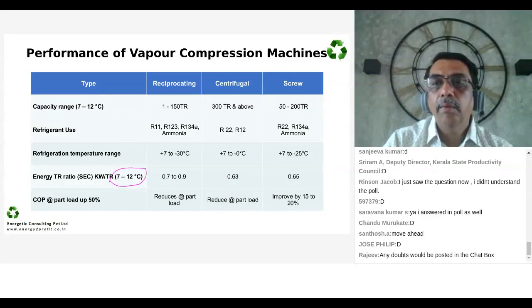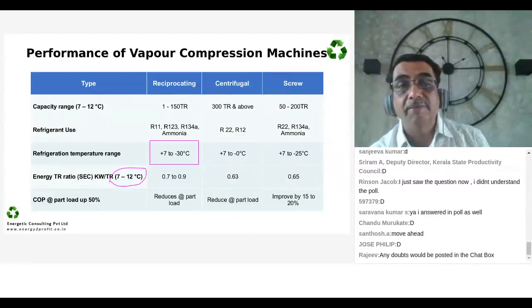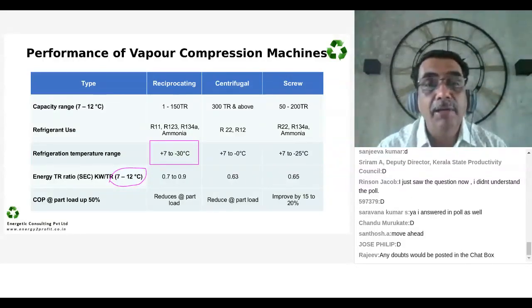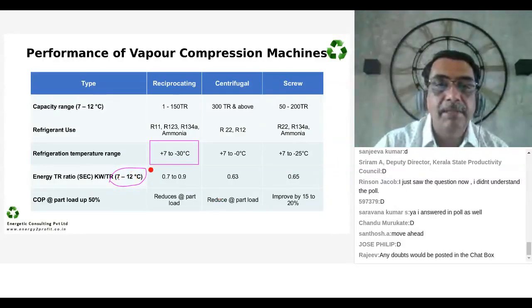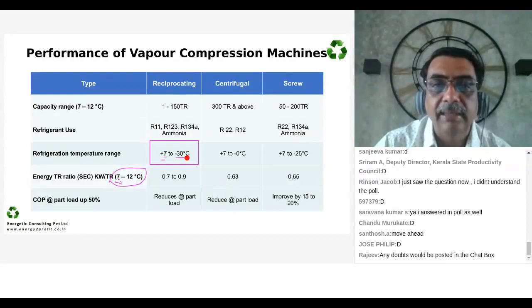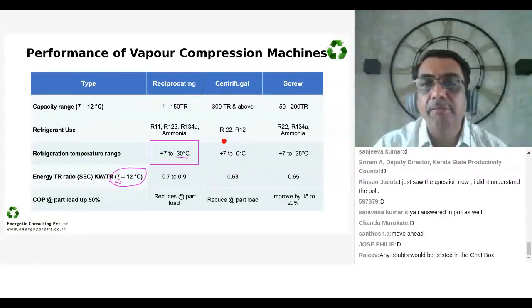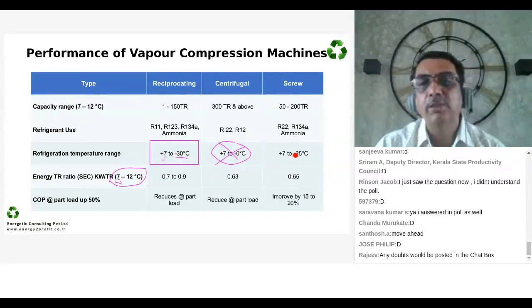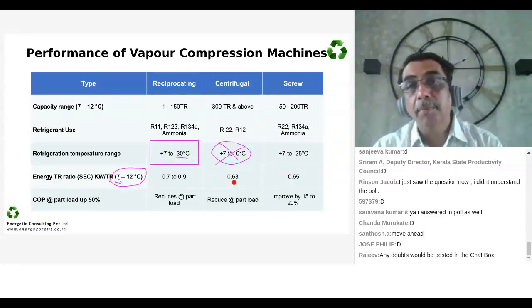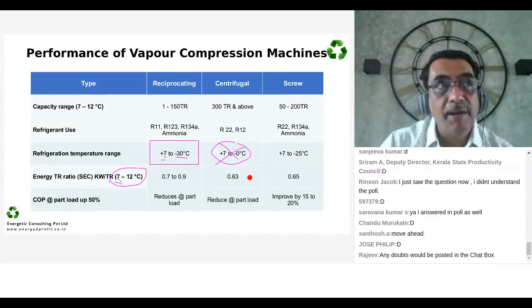Now, if you look at this, I am not referring to a temperature range of only 7/12 as a case, that is +7. I am referring to a case where the temperature, like this temperature 7 is this temperature here. This 7 is this temperature. But what if the temperature is -30? These systems are not as effective. One would not recommend centrifugal to go for -30. Screw can work up to -25, right? Now centrifugal performance on the other hand can go as low as 0.5 kilowatt per TR.